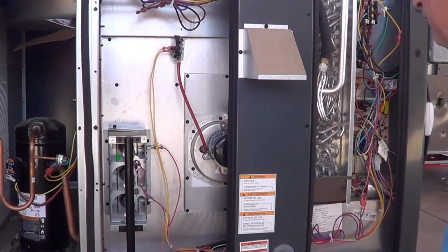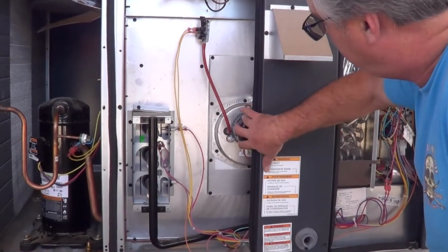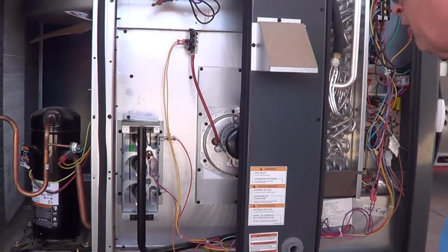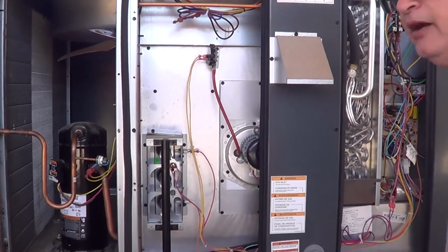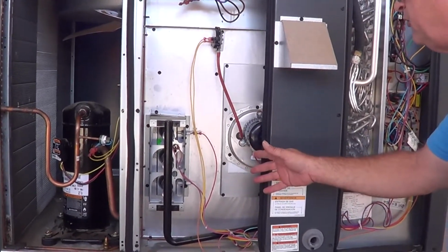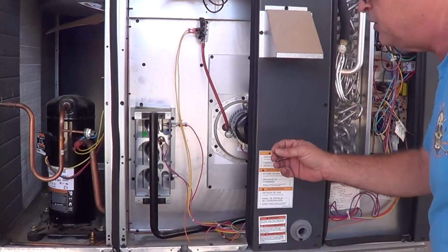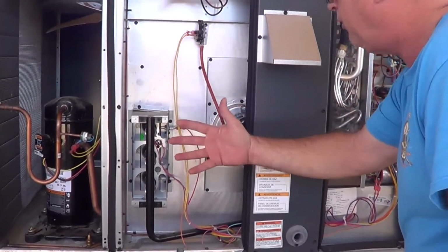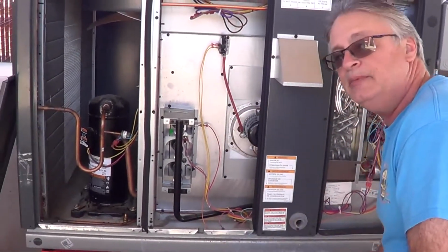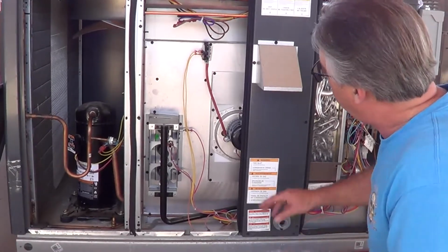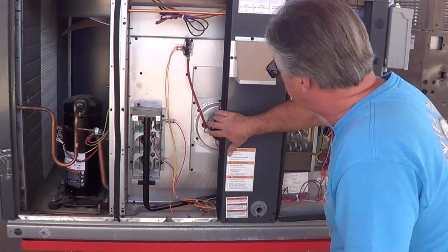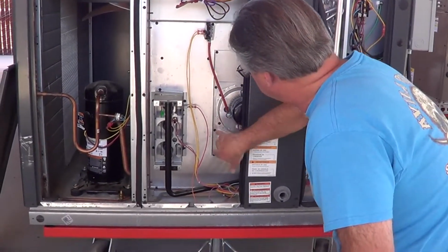It is very important that we prove that this is turning and pulling air through the heat exchanger before the ignition process. Otherwise, if we don't have the proper airflow through and we do the ignition process, we might have a flame rollout situation where the flame would actually come backwards out of the heat exchanger trying to seek oxygen, and it could damage our components in here. So that's why it's vital that the first step before the ignition process is to prove that this inducer fan motor is operating.